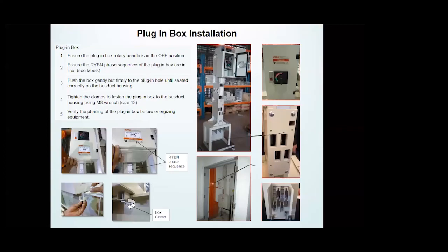Apart from joint installation, we also have plug-in box installation. You need to ensure the plug-in box rotary handle is in the OFF position during installation. You also need to ensure the R, Y, B, N phase sequence of the plug-in box is in line. Our plug-in box is equipped with an earth bar for additional safety — when connecting with our busway system, the earth bar will make contact first and disconnect last.